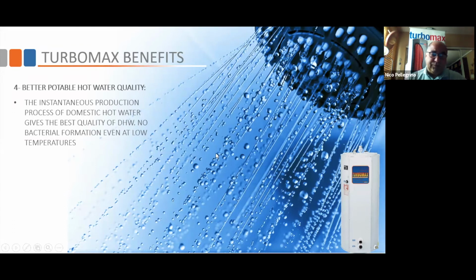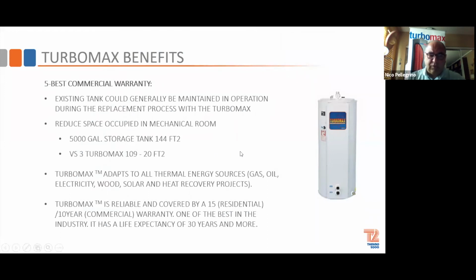So the quality of water is impeccable due to the fact that there's no scale in the tank, and also there's no chance of Legionella growing in the tank, because we have no surfaces of scale for Legionella to grow. The other thing is engineers and architects like the space that we take. A 5,000 gallon storage tank is roughly 144 square feet. 3 Turbomaxes are only 20 square feet. So you can get the tank up in an elevator, up into a mechanical room through a door. You don't need cranes, and it also can be adapted to many energy sources. So it's 15 years residential and 10-year commercial, non-derating. So that means full output from start to finish.